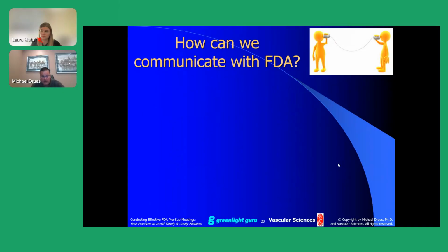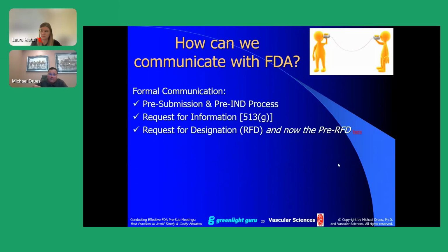So how do we communicate with FDA? In terms of formal communications, we have the pre-submission for medical devices that we're talking about in this webinar. The equivalent of that is the pre-IND meeting for drugs. We can do a 513(g), a request for information. I'm not a big fan of the 513(g) for a bunch of reasons.